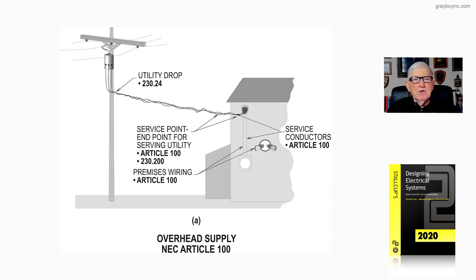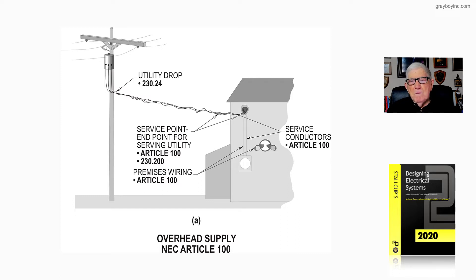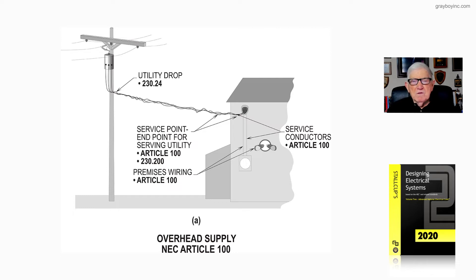Notice in the illustration the transformer on the pole. We have a utility drop in accordance with 230.24 over to the weather head that is installed there at the building. At the weather head, we make connections to the conductors fed through the weather head, and that's the service point going down to the meter and into the service panel of this facility.